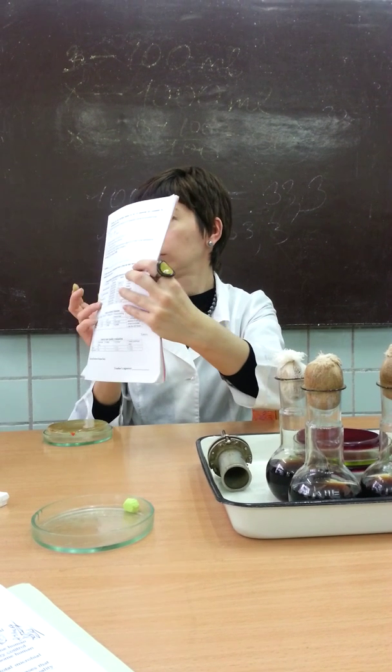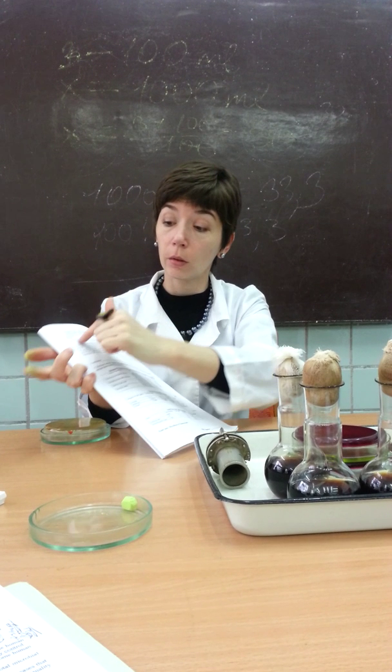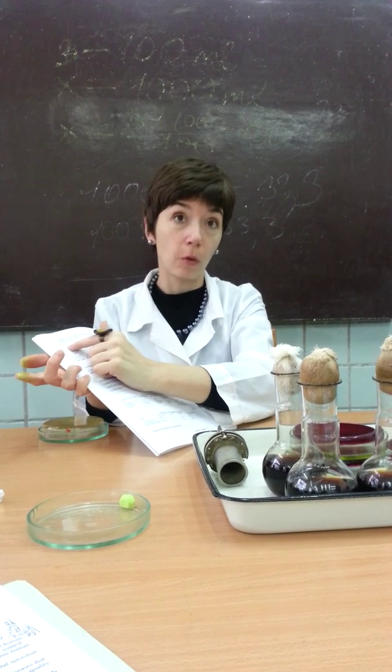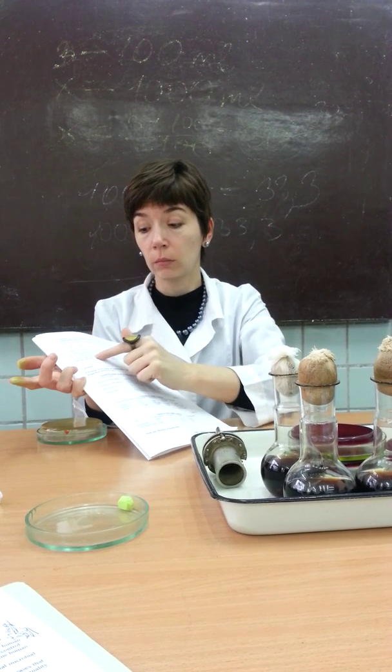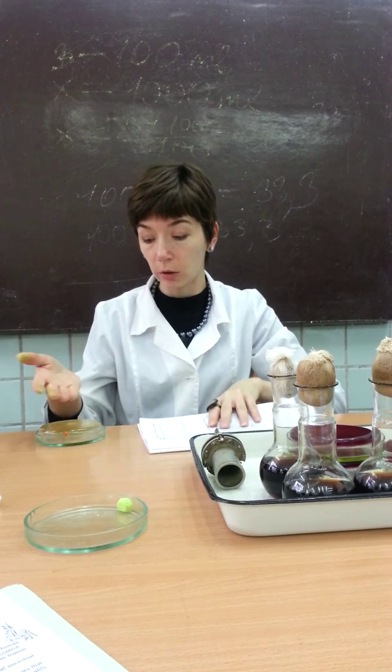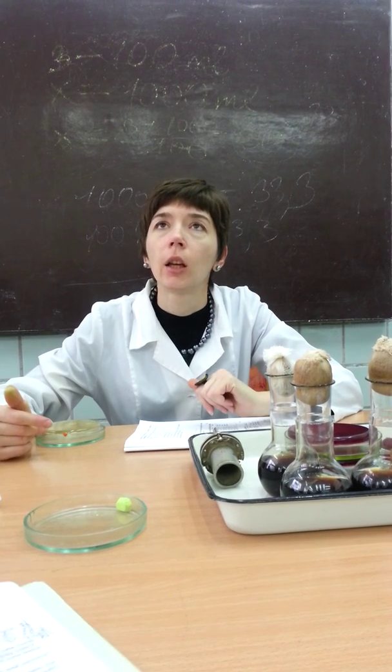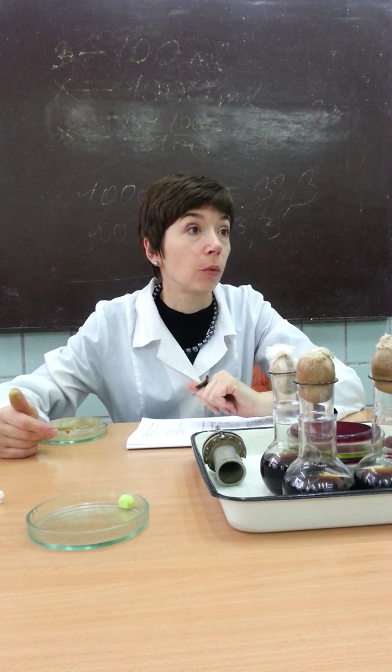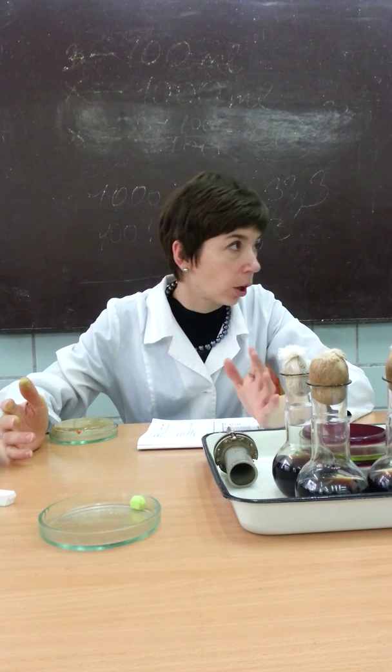In the formula, A is the number of colonies counted, and the result is usually about 1,000. It's normal for usual rooms until 2,000, up to about 4,000. But for an operating room, it's not normal.